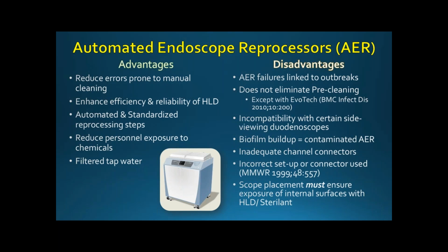Some of the disadvantages are that biofilm can build up in the AER. That's why you need to read through the manufacturer's directions to see how frequently they need to be cleaned, especially the connectors used to connect the different scopes to the equipment. There's one that eliminates the need for pre-cleaning, but for the majority of them, that pre-cleaning step is so critical to get done. And then you have to make sure the scope is placed appropriately and you use the right connectors, because otherwise you're going to have issues. All of those things are so important to making sure you get what you need done.